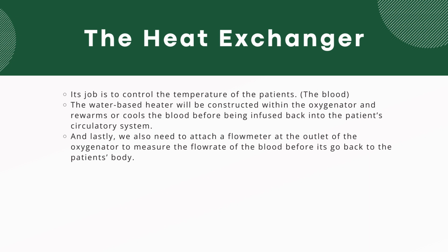The next part is a heat exchanger. Its job is to control the temperature of the patient. So, in other words, it controls the blood temperature. The heater is a water-based heater, constructed within the oxygenator, and it rewarms or cools the blood before it is infused back into the patient's circulatory system. So in summary, we have the drainage cannula, we have the pump, we have the oxygenator that connects to the control system, and we send the blood back to the body via the return cannulas. And lastly, we also need to attach a flow meter at the outlet of the oxygenator, to measure the flow rate of the blood before it goes back to the patient's body.